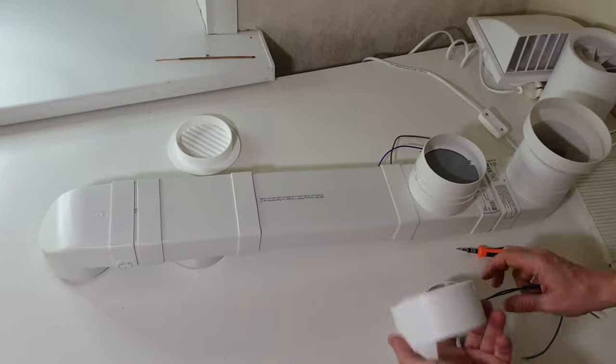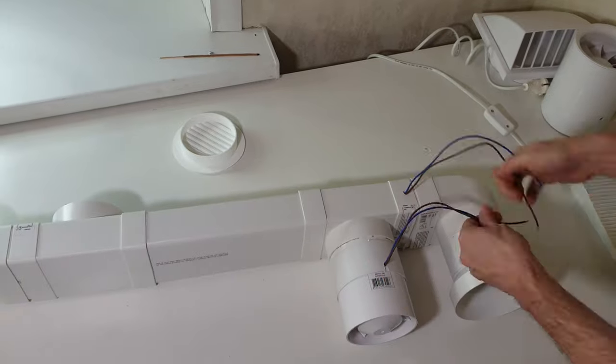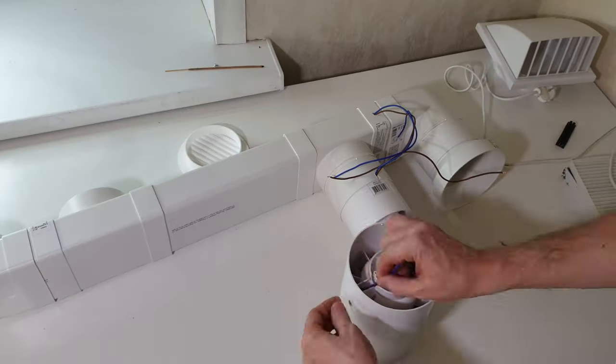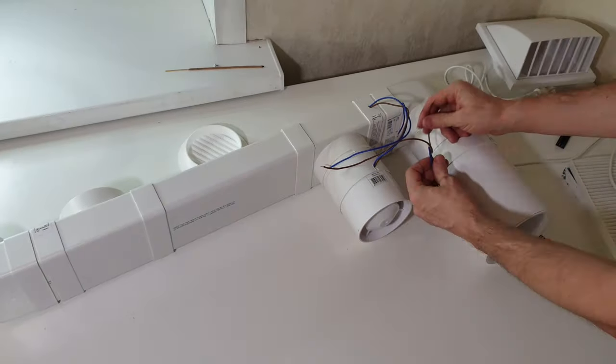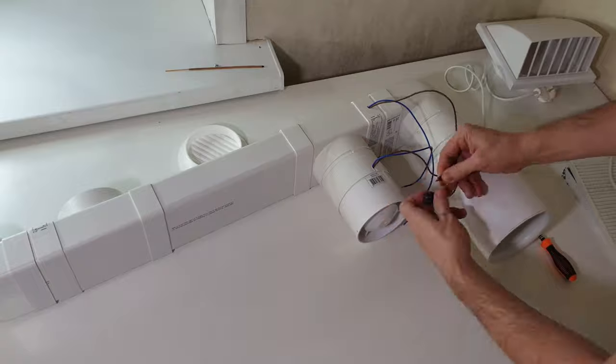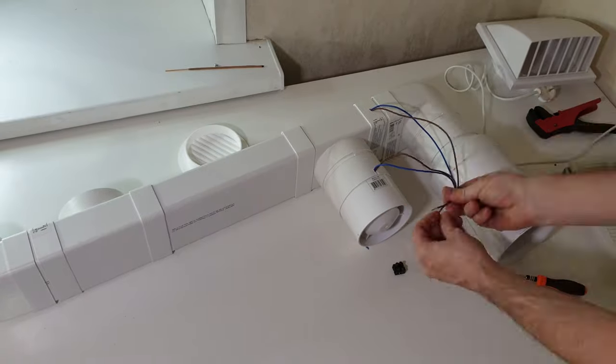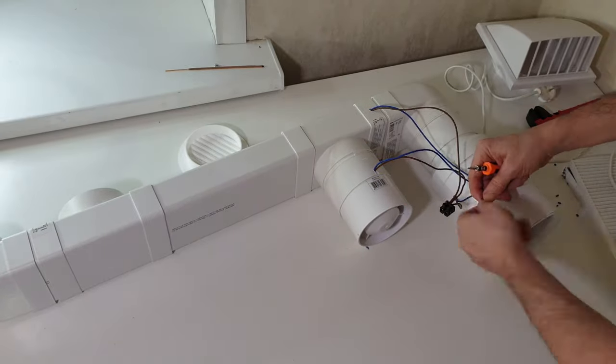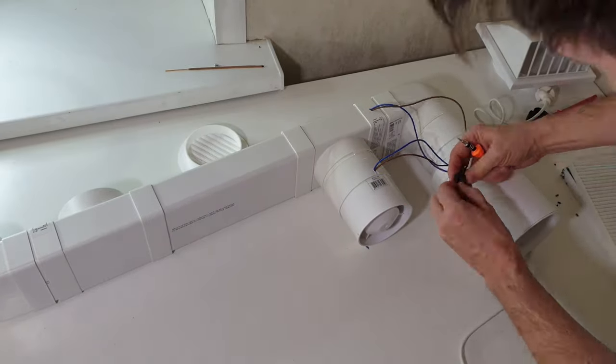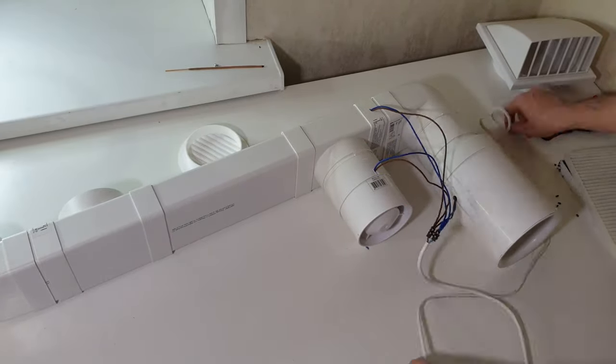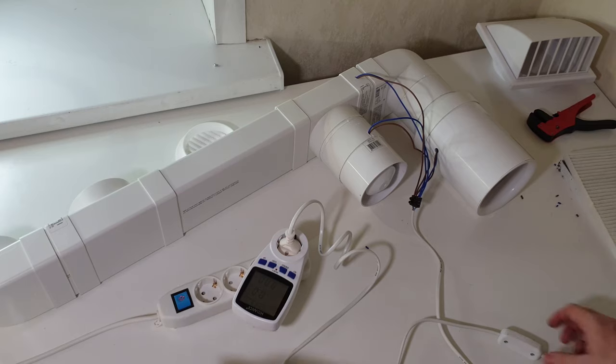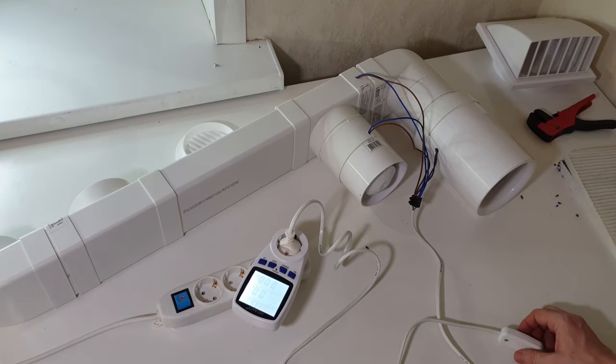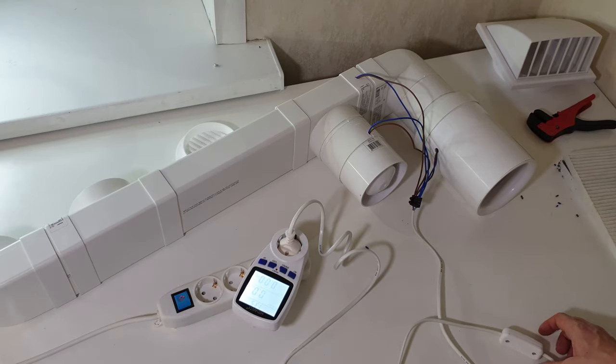Now, we complete the wires and you can conduct tests. Current consumption at the beginning of 60 watts. Later, when the cable heats up, it'll be around 30 watts.